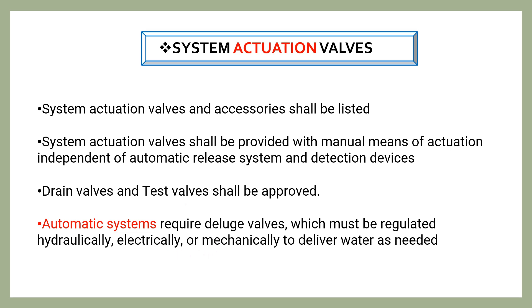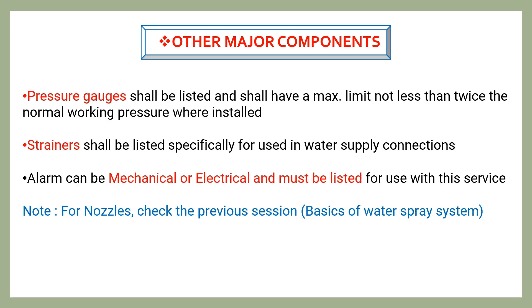Other major components include pressure gauges, strainers, and alarm bells. For nozzles, you can check the previous session on basics of water spray system. Pressure gauges shall be listed and shall have a maximum limit not less than twice the normal working pressure at the installation point. Strainers shall also be listed and are specifically used in water supply connections. Alarm bells can be mechanical or electrical — in electrical form we can use horn strobes — and they must be listed for use with this service.